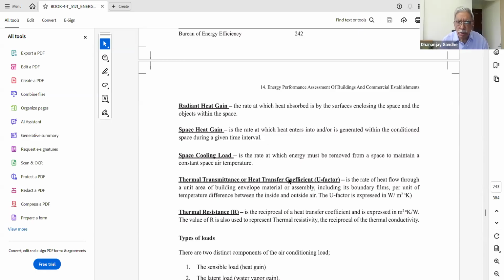There are two factors which are very important and always used in building design, also civil and architectural building design. They are thermal transmittance, or the heat transfer coefficient, usually expressed in terms of U factor. It's a very popular term for the architect. The U factor is the rate of heat flow through a unit area of a building, that means the wall or the roof, so unit heat flow taking place per square meter. So heat is not expressed in heat units, but in terms of watts per m square. So watts per m square is the thermal transmission, or the heat transfer coefficient.